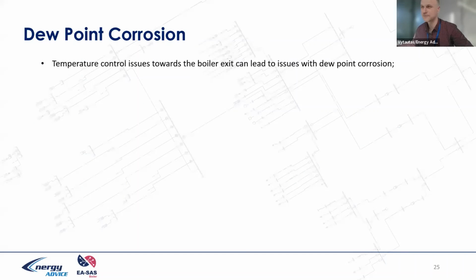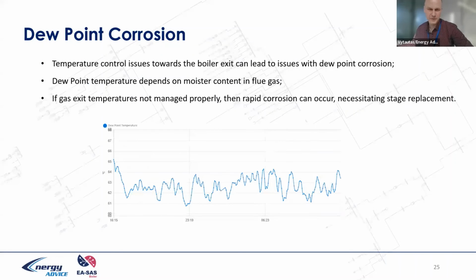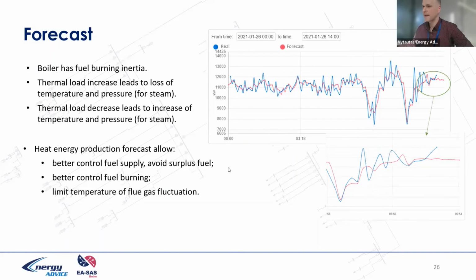Dew point, of course, we calculate the dew point temperature from the flue gas, and we can monitor this. Forecast also: if we have load, especially for industrial, or not only industrial but district heating applications, sometimes it's very good to know when the boiler would increase or reduce its capacity, and to control a little bit in advance.